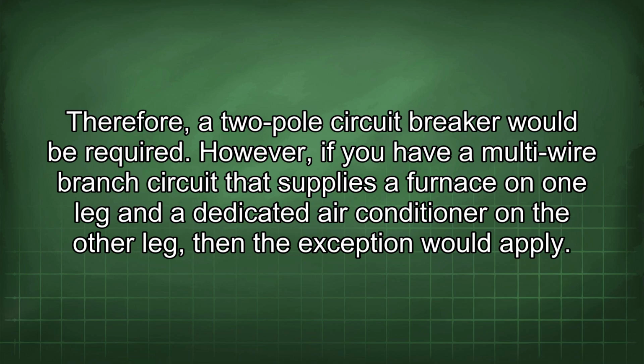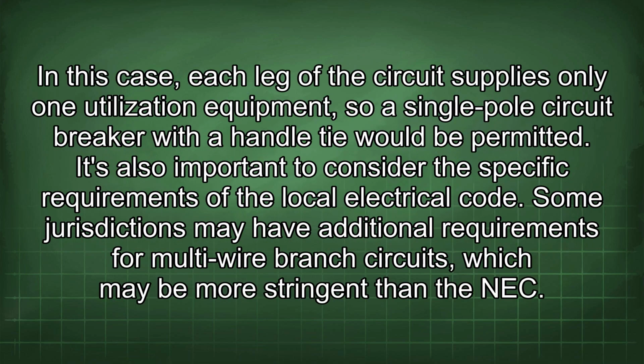However, if you have a multi-wire branch circuit that supplies a furnace on one leg and a dedicated air conditioner on the other leg, then the exception would apply. In this case, each leg of the circuit supplies only one utilization equipment, so a single-pole circuit breaker with a handle tie would be permitted.